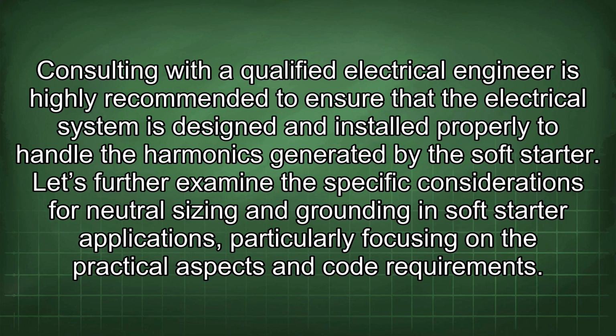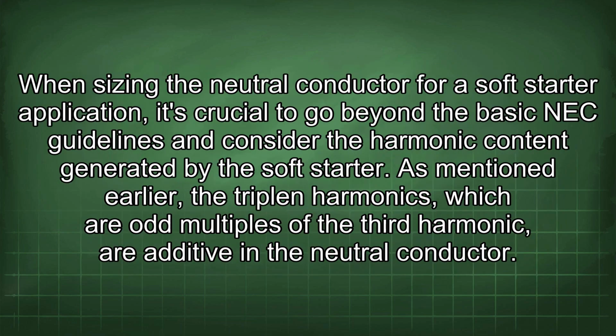Consulting with a qualified electrical engineer is highly recommended to ensure that the electrical system is designed and installed properly to handle the harmonics generated by the soft starter. Let's further examine the specific considerations for neutral sizing and grounding in soft starter applications, particularly focusing on the practical aspects and code requirements. When sizing the neutral conductor for a soft starter application, it's crucial to go beyond the basic NEC guidelines and consider the harmonic content generated by the soft starter.